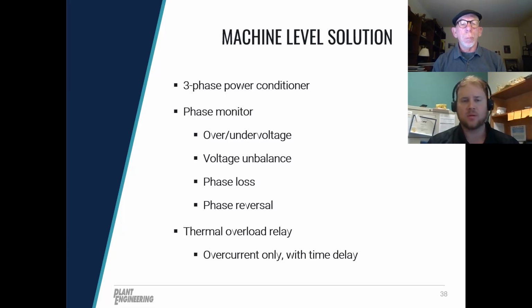Where phase monitors sense voltage, overload relays sense current draw. We talked earlier many times about what excessive current draw can do to a motor. None of it is really good. So if you have a critical motor application that gets overloaded, you could always install an overload relay in that circuit to protect the motor and the branch circuit. Maybe there are other components, not just the motor itself.